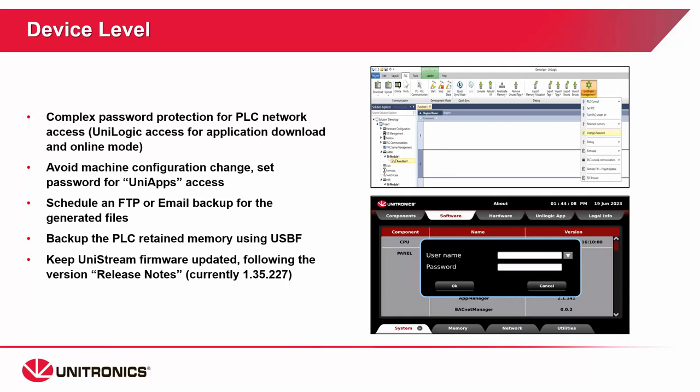Let's talk about device-level features that are available. UniLogic will now require that the user set an access password for each unit. You can change the password on first access when you go to download, or under UniStream Management, change password. It can also be set in UniApps. Anytime UniLogic goes to connect from a new device, the password will be requested. UniApps is the backdoor set of screens for UniStream — it has things like network configuration, tag access, and IO access. Unitronics recommends password-protecting the UniApps screen, from just a UniApps password to UAC, user account access.